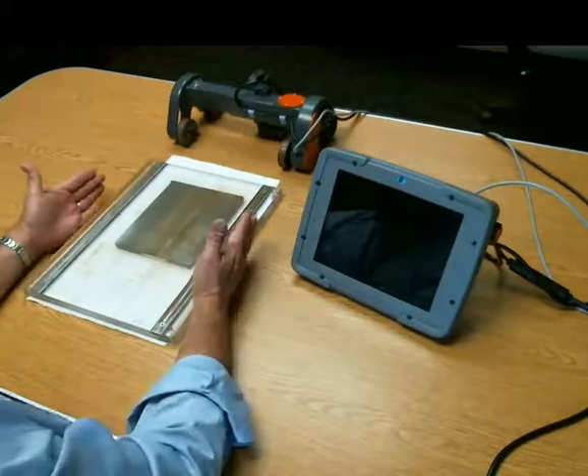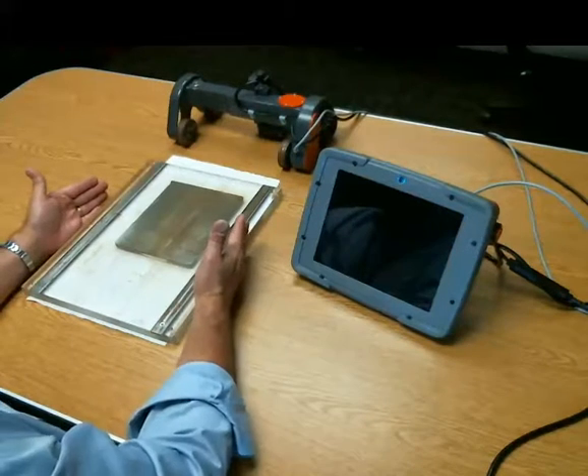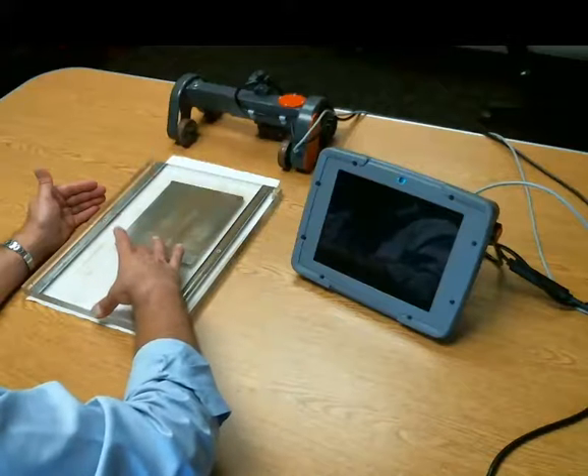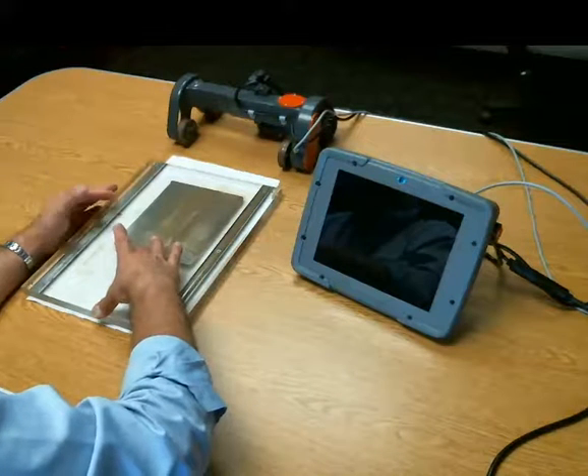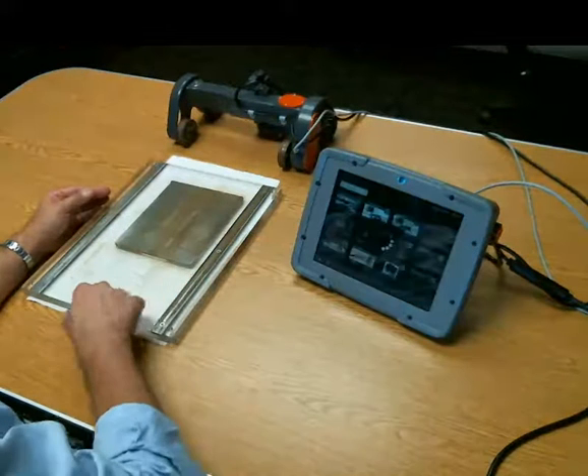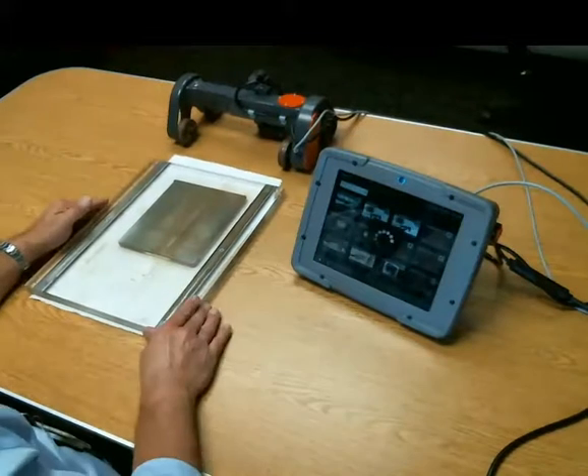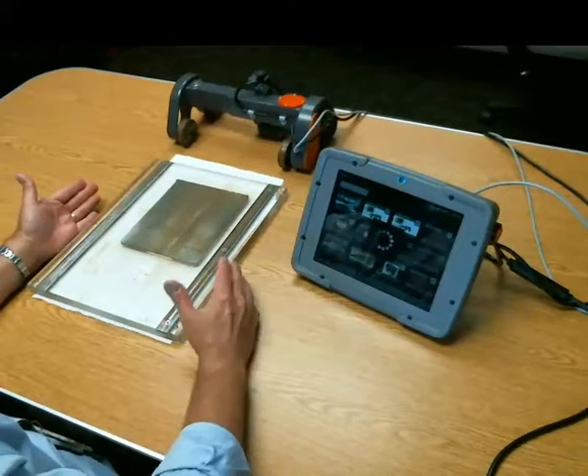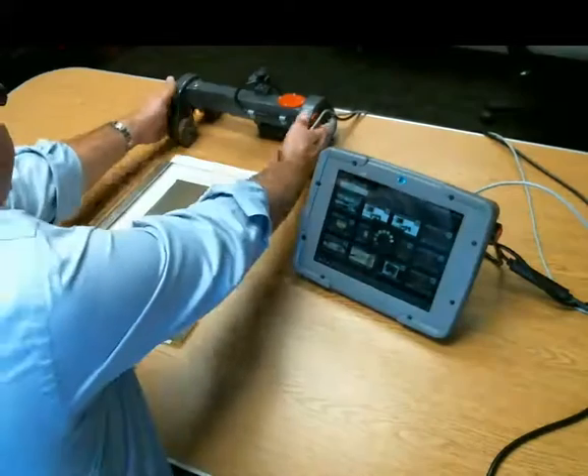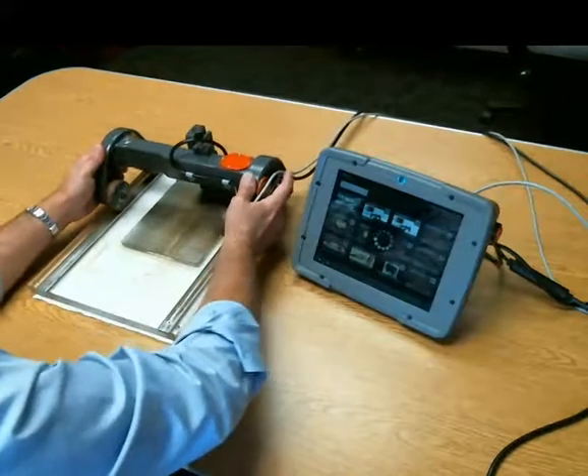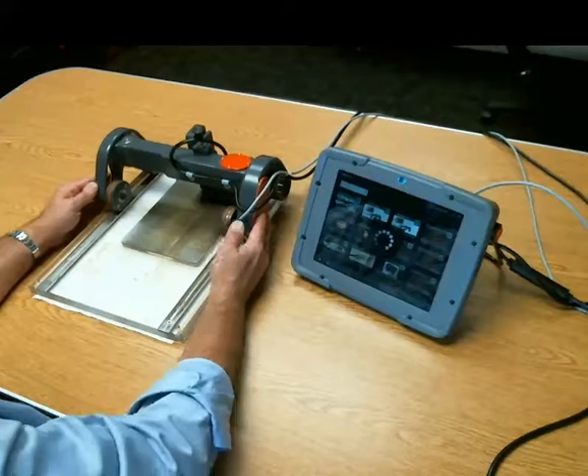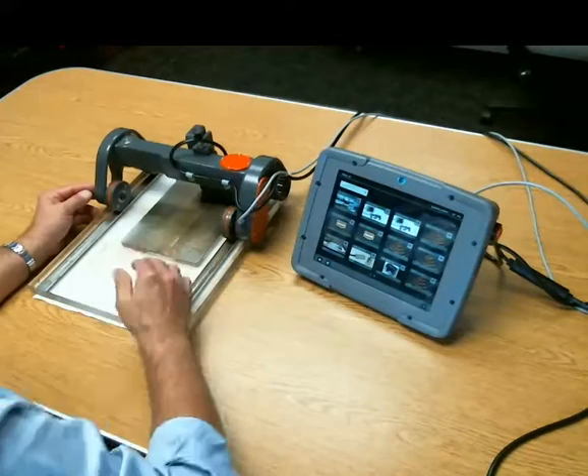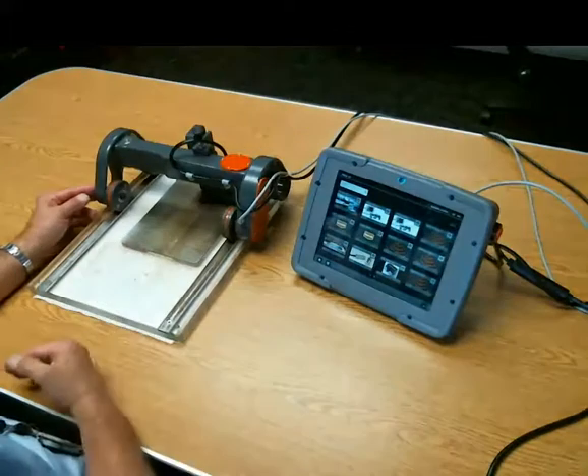Now, one important thing when you start with your demo plate, there are two ends to this obviously. One end has a lot more Lexan between the block and the edge, the GE logo on it. You want that facing you. Everything with the demo application and so on is made for this orientation. You want to put the encoder trolley on the rails with the probe facing away from you, the GE logo on the block facing towards you.